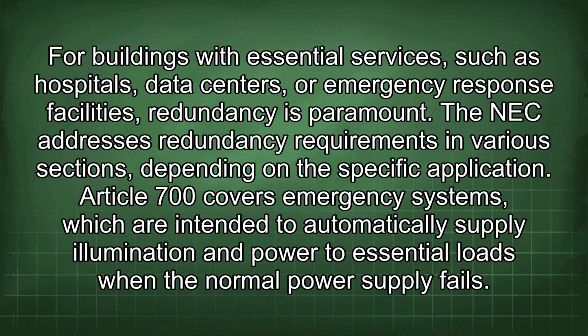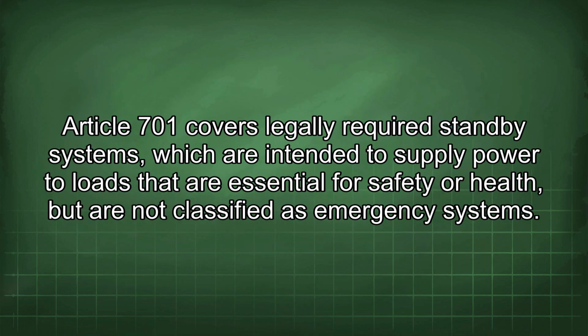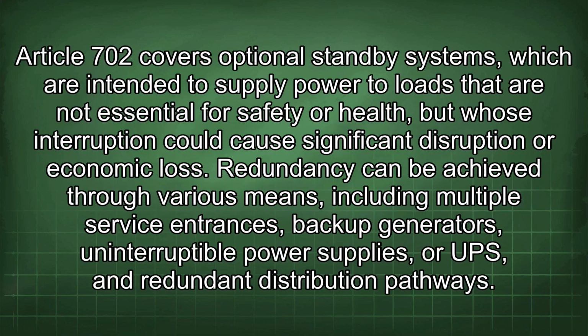Article 700 covers emergency systems, which are intended to automatically supply illumination and power to essential loads when the normal power supply fails. Article 701 covers legally required standby systems, which are intended to supply power to loads that are essential for safety or health, but are not classified as emergency systems. Article 702 covers optional standby systems, which are intended to supply power to loads that are not essential for safety or health, but whose interruption could cause significant disruption or economic loss.